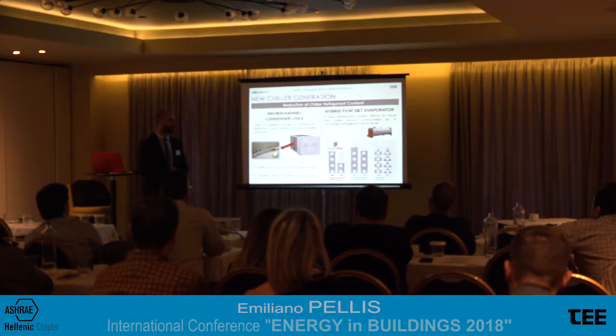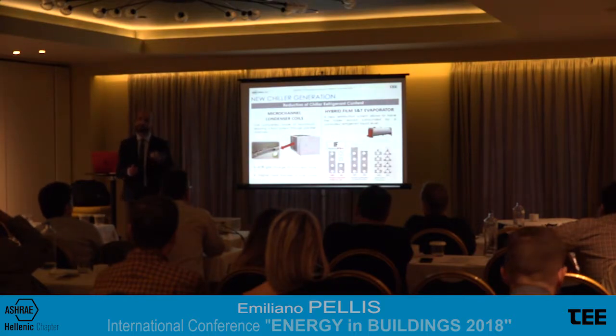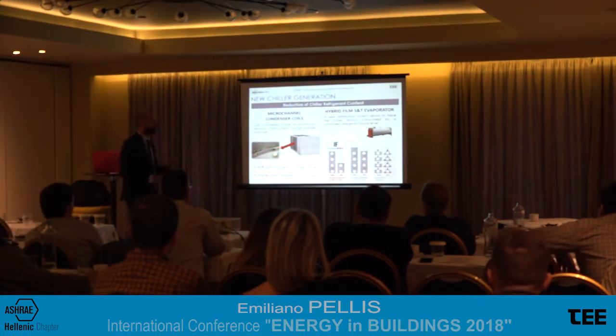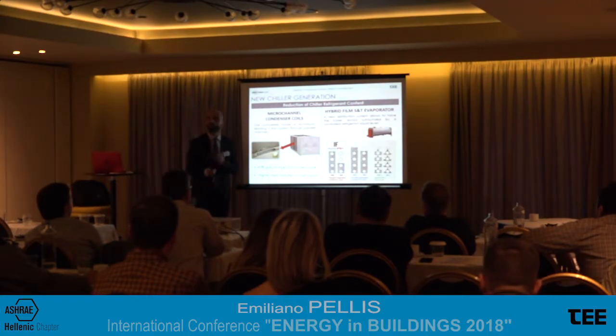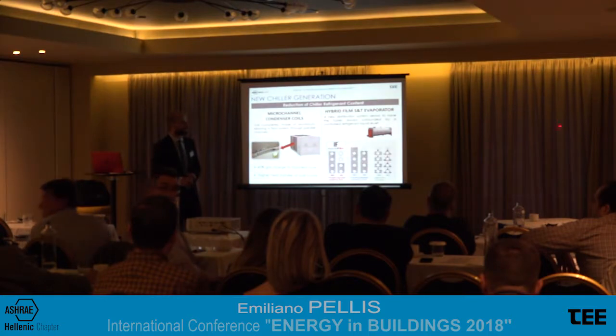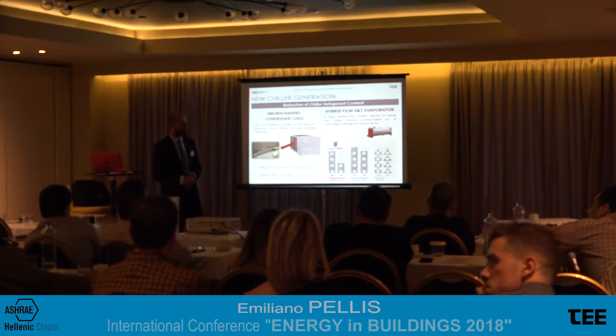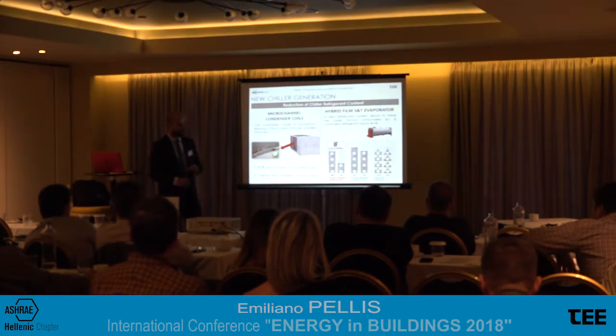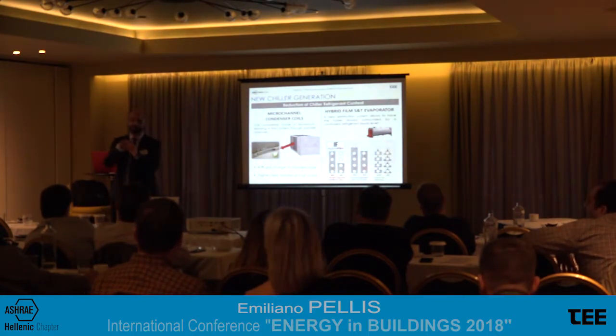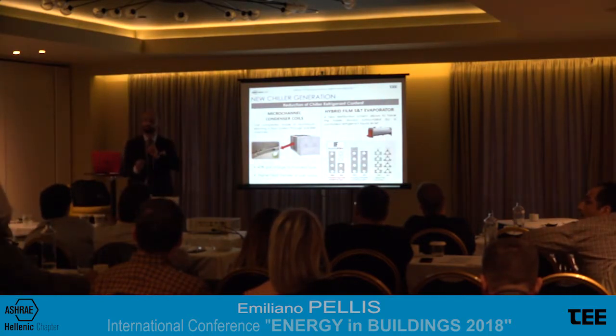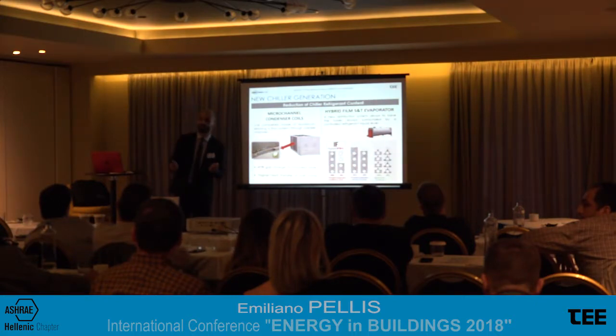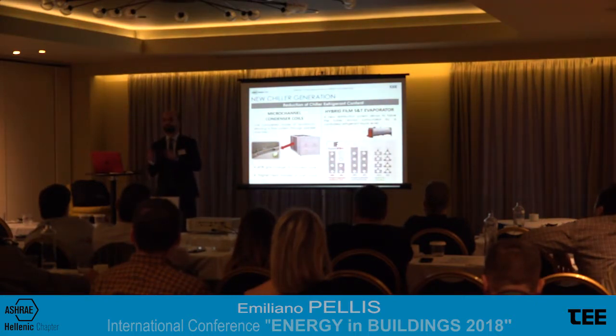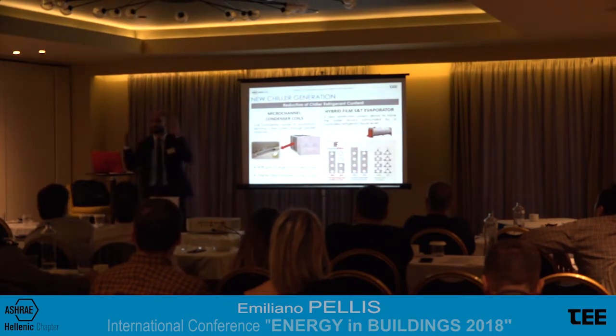The hybrid film is a technology where, thanks to a special distribution system, we achieve very good performances similar to the flooded, but we limit the quantity of refrigerant that we need, resulting in a total reduction of 35–40% of the total refrigerant content. Basically, thanks to the distribution system on the top, we have the pipe, and we try to have around the pipe only the minimum quantity of refrigerant that is needed for the process. To talk very practically, the difference between the flooded and the hybrid film is like a relaxing bath and a fast shower. Okay, we need less water in the second case to reach the same effect, to clean ourselves.